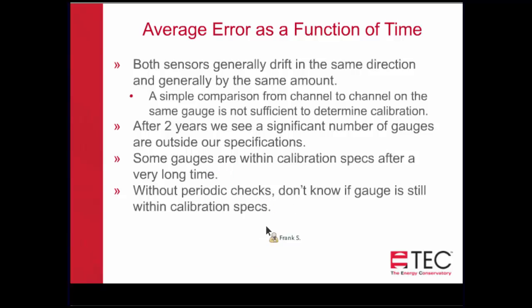So what have we learned with some of this data? We know that both sensors will generally drift in the same direction and generally by the same amount. So it's not sufficient to just do a comparison of one channel to the next to see, well, is channel A that much different than channel B? Because what we know from our experience is that they will both be off by the same amount. So it's not likely that you'll be able to determine much just by doing a comparison from channel A to channel B.